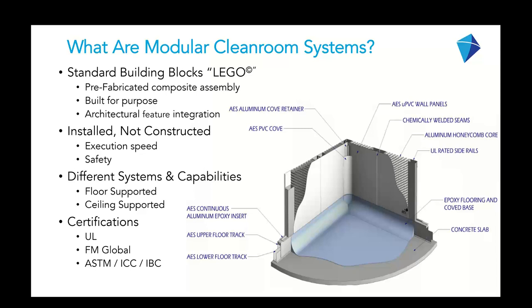When you start modifying a facility, particle generation, as we've all experienced whether in our homes or on these projects, proliferates everywhere—and that's a nightmare for an existing facility through an air handler intake. You just don't want it. So flexibility in terms of material, not just from a unit 'Lego' type approach to modifying the facility by removing or changing unit pieces, but also from a material and cleanliness maintenance standpoint, reduces the burden of making modifications. It's much more straightforward to requalify areas once a modification has been made, so I want to stress that point.